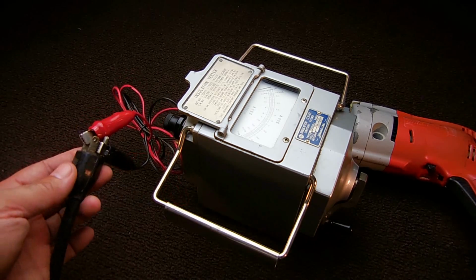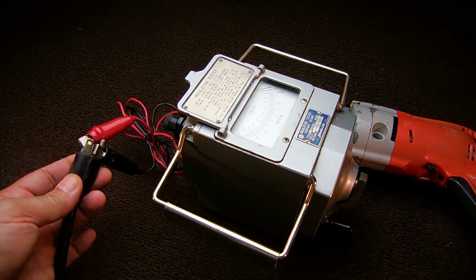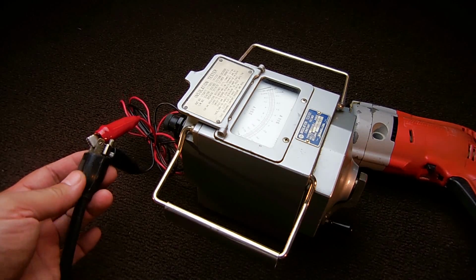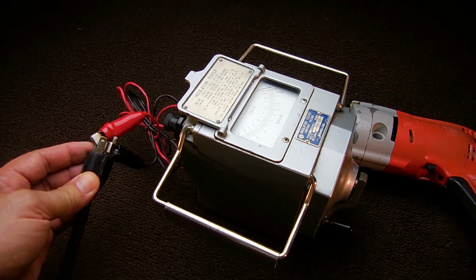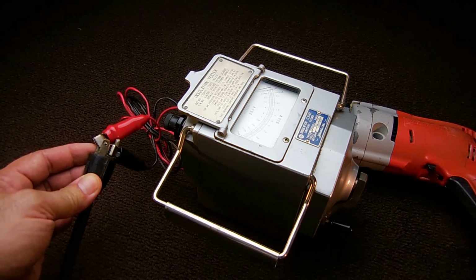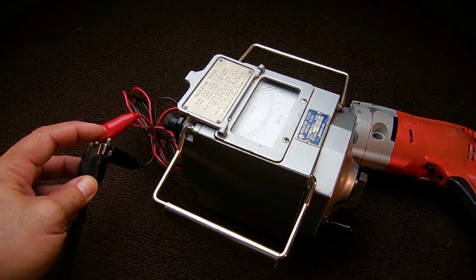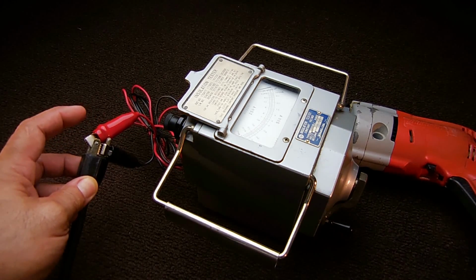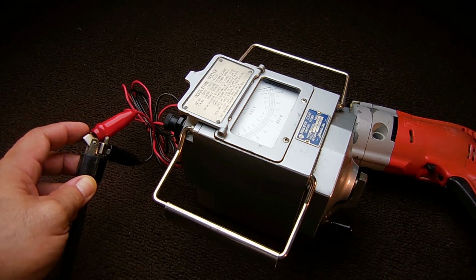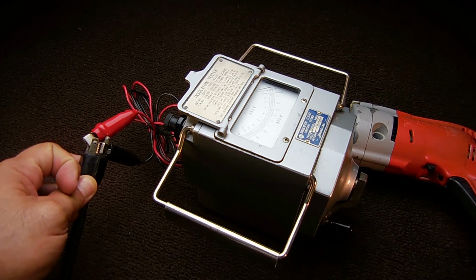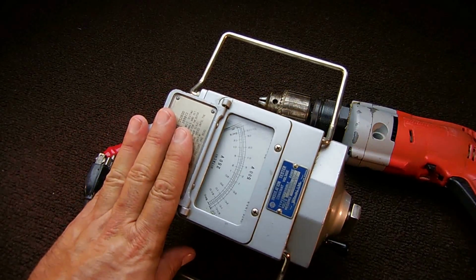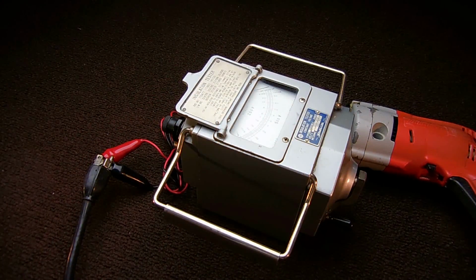If you have a problem with an AC compressor that tends to overheat or trip the breaker, you're going to turn power off to that unit, discharge the capacitor, remove the blade connectors from the compressor, and you're going to check between each one of the terminals and ground. You should have very high readings on the Megger. Now let's take a look at the electronic version.